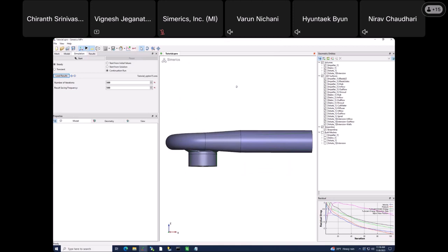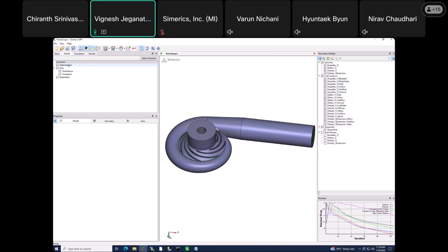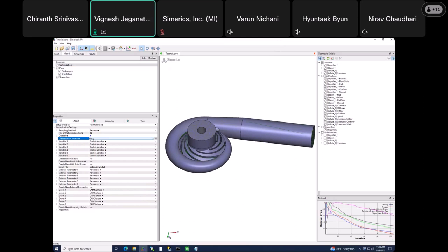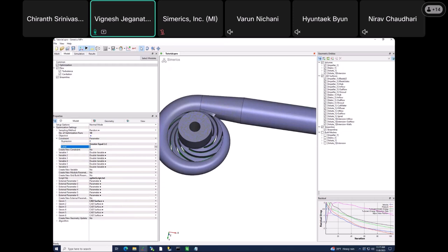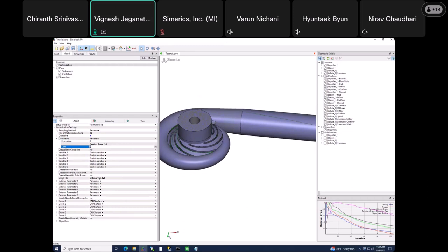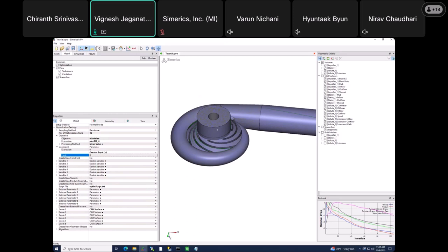You can add a constraint saying head should be greater than or equal to some minimum value, and Simerics will factor that into the optimization. Right now we only optimized efficiency without any head constraint, so it's easy to set up — any constraint you want can be added, even manually created parameters. Let me create a section plane to see how the pressure field looks. You can study the best and worst performing cases. For example, the 7th design with low efficiency shows a lot of recirculation and low pressure areas — which explains the poor performance.